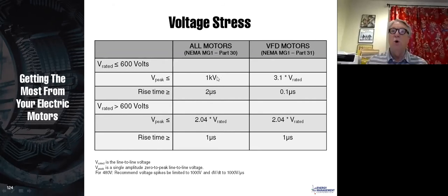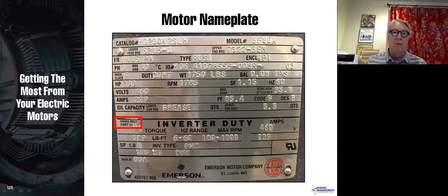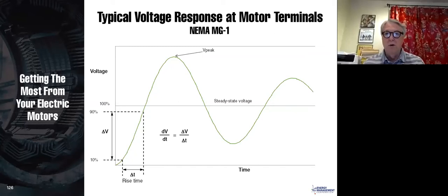And the insulation is rated for 1 kV and a rise time of 2 microseconds. If you get a VFD rated motor, it has premium insulation in it. We call that in the industry high spike wire. And the high spike wire has to be rated for 3.1 times the rated voltage of the motor, and it's good for a 0.1 microsecond rise time. Now, generally, we just look at the voltage. So this is 1 kV, and for a 480 volt motor, I'm going to call this 1600 volts because most high spike wire is rated for 1600 volts, although 3.1 times V rated is a little bit less than that. So I'm giving you the actual wording in the standard. Again, this is the Emerson nameplate, and I'm reminding you here, it says NEMA MG1 Part 31. That means it has the premium insulation for use with a variable frequency drive. In NEMA, this is how you measure the rise time.